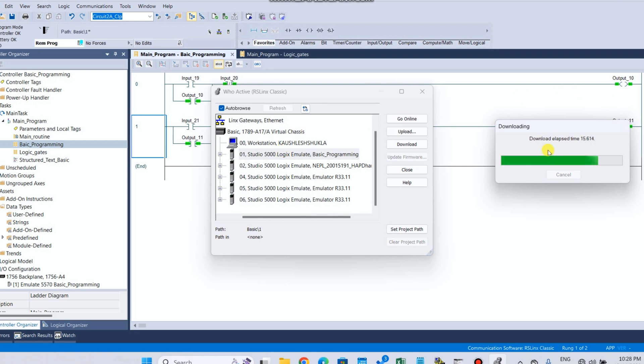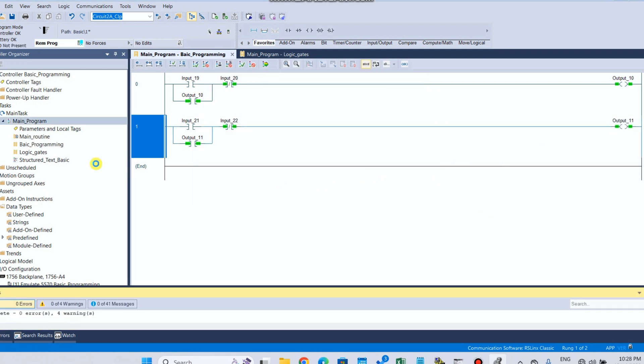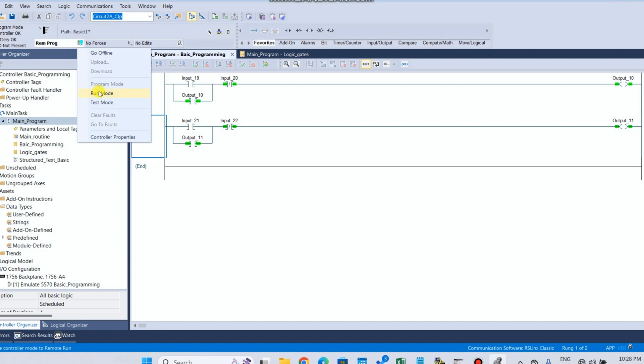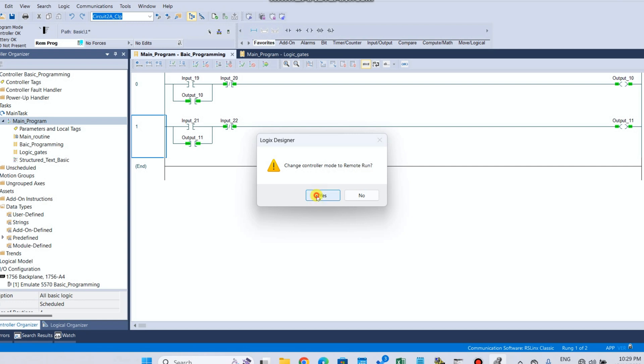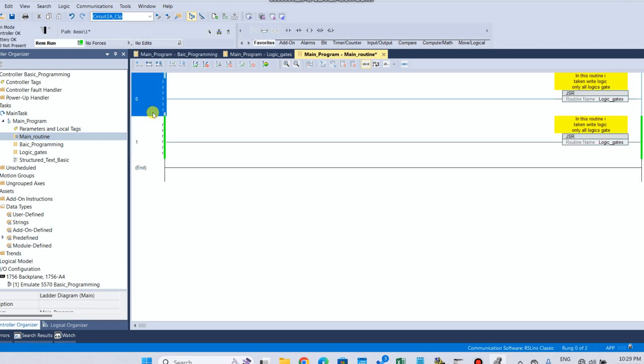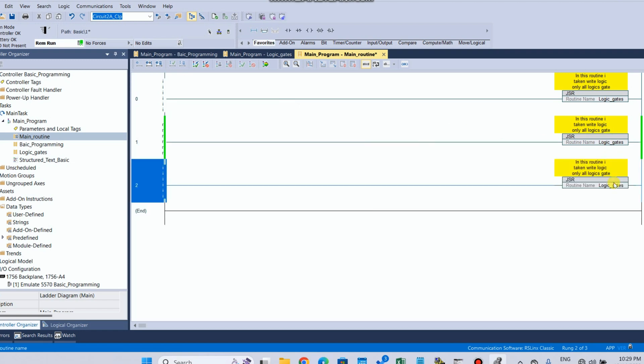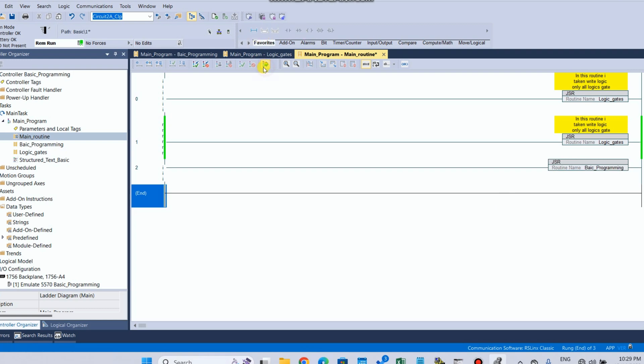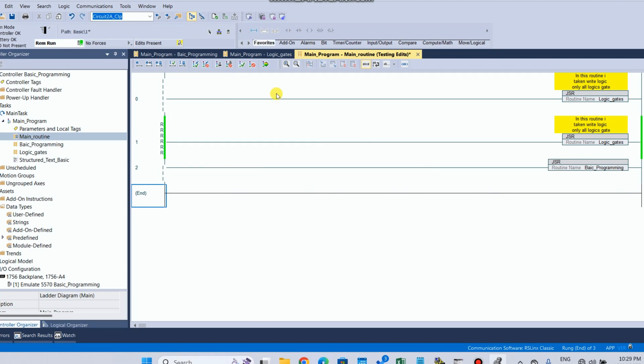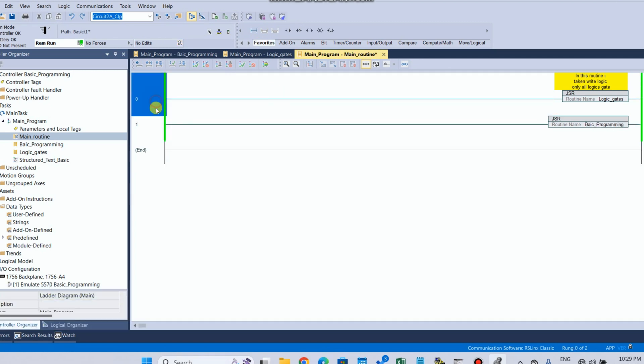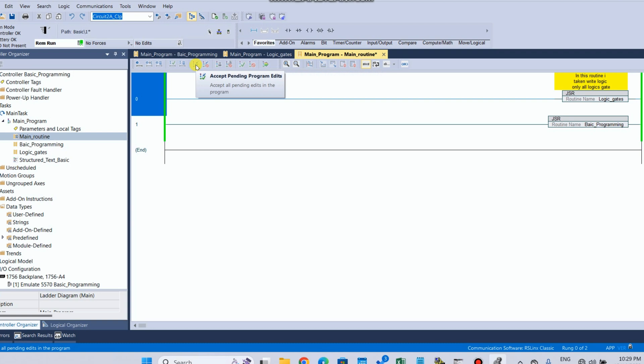We can see the program is finalizing and it has been downloaded. Now change the controller from remote run mode to program mode, then from remote program mode back to remote run mode. Change the controller mode to run mode. In the main routine we have required a subroutine linked to the main routine. Always remember: if any change is made in the program, we need to first accept all edits, then finalize all edit programs.